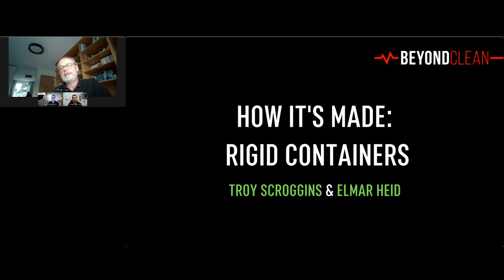The heat storage capacity and heat conductivity of plastic material is by far not as good as aluminum. That means aluminum supports the drying during and after sterilization. This is one big thing. Secondly, plastic materials get more affected by cleaning chemicals, or at least in a different way, more than aluminum surfaces.